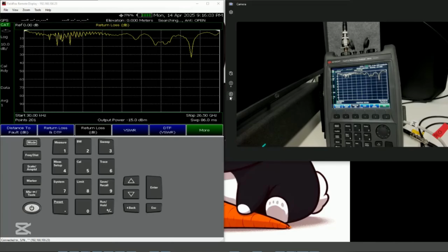You might have heard this from the expert from Keysight to have a quick test on your measurements before you do calibrations, because back in the days when I got this unit, I would run a calibration straight away. That is not the best sequence because we might need to change some of the parameters like power, number of points, frequency, things like that. And if you change any of that after the calibrations, we need to recalibrate again. So the best thing is that you verify the measurements that you want and make sure that that's what you want in terms of all the setup, like bandwidth, number of points, start frequency, power level, things like that. Only then you remove the cable, then you run the calibrations, then you do a final measurement.